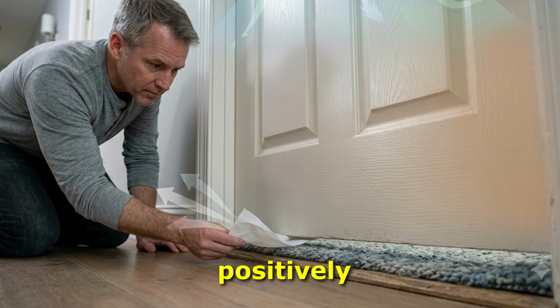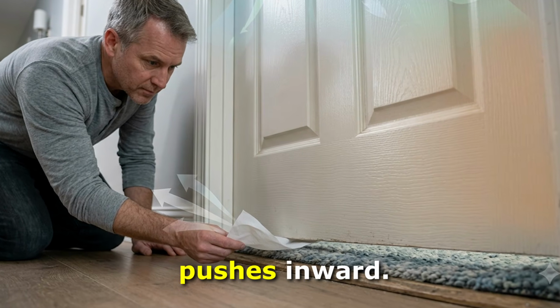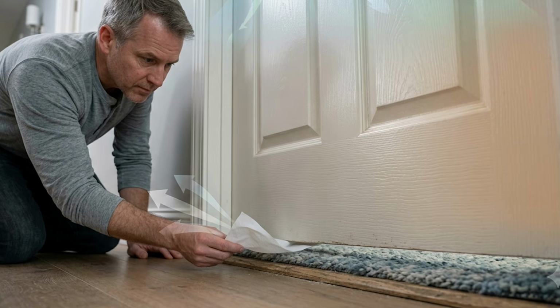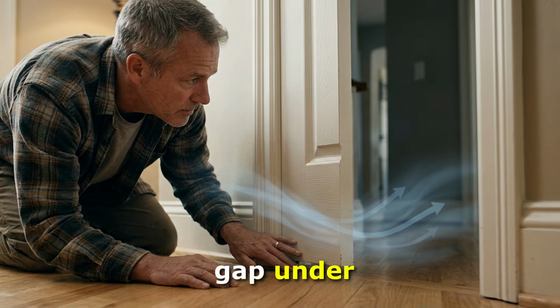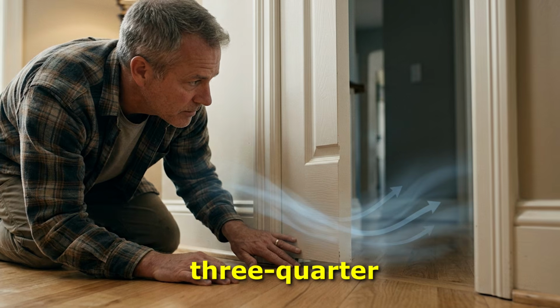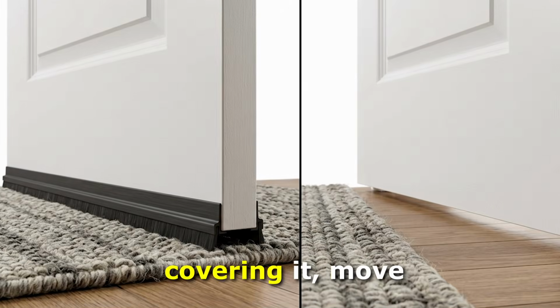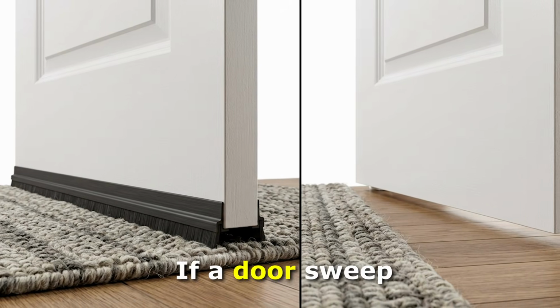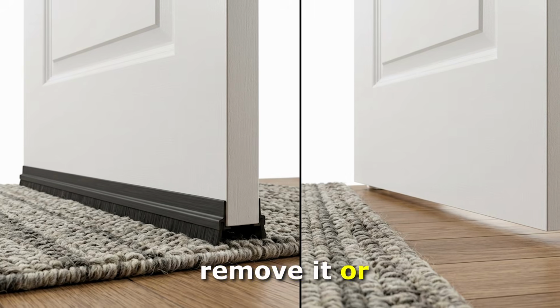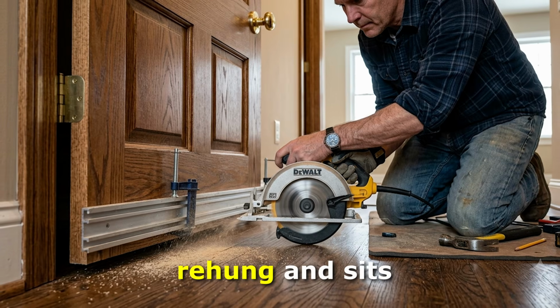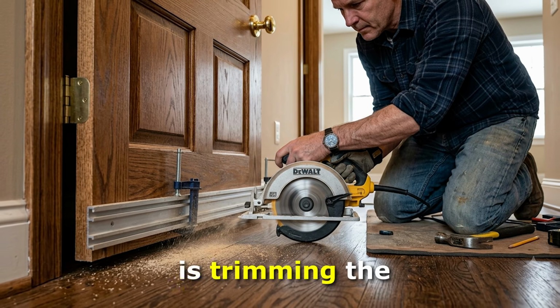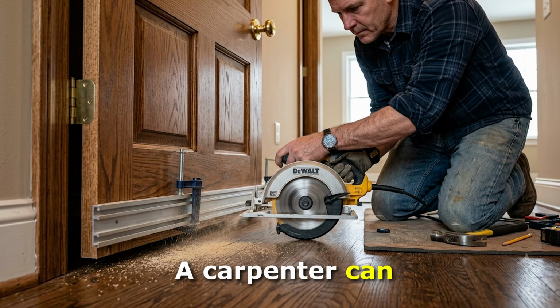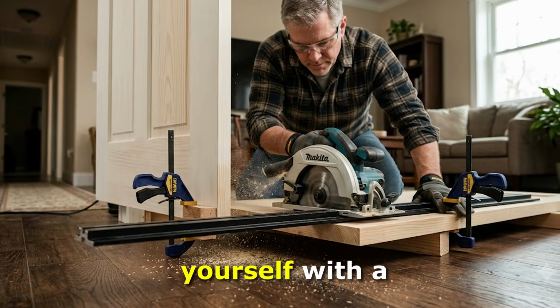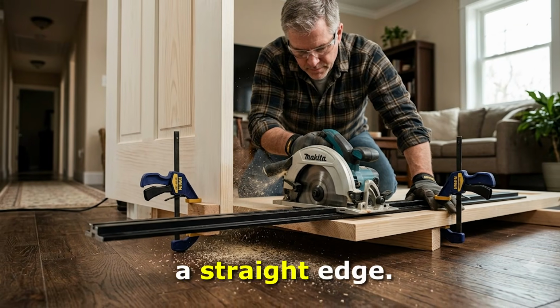If the room is positively pressurized, tissue pushes inward. Start with the door. Get on your knees and look at the gap under the door. It should be at least 3/4 inch. If a rug is covering it, move the rug. If a door sweep is blocking it, remove it or raise it. If the door was rehung and sits too low, the fix is trimming the door bottom. A carpenter can do it in an hour. You can do it yourself with a circular saw and a straight edge.